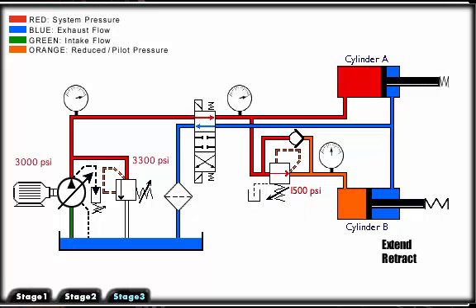At this point the valve begins to close off, limiting any further buildup of pressure. As fluid bleeds to the tank through the valve drain passage, pressure will begin to decay off and the valve will again open.